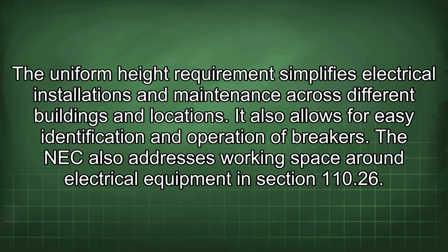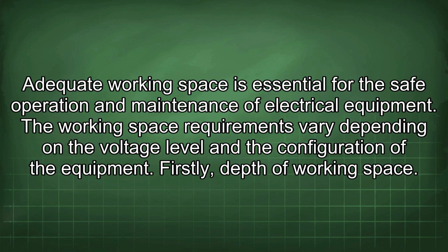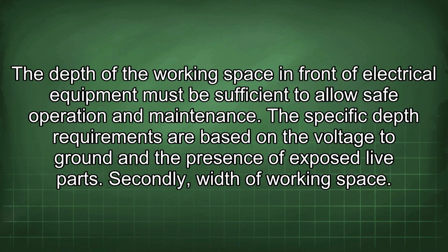The NEC also addresses working space around electrical equipment in Section 110.26. Adequate working space is essential for the safe operation and maintenance of electrical equipment. The working space requirements vary depending on the voltage level and the configuration of the equipment. Firstly, depth of working space. The depth of the working space in front of electrical equipment must be sufficient to allow safe operation and maintenance. The specific depth requirements are based on the voltage to ground and the presence of exposed live parts.